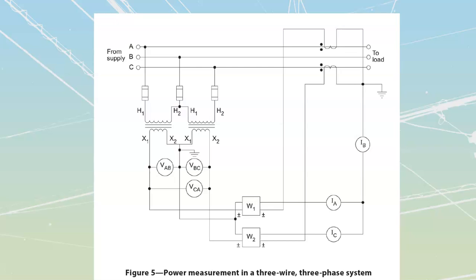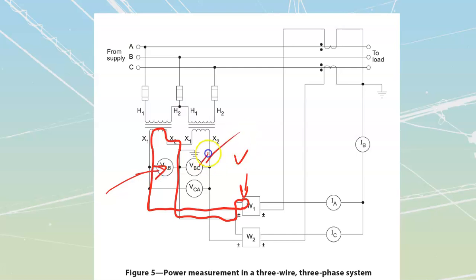Looking at my currents over here, we're just going to trace over top of stuff once again. Looking at this line over here coming from my watt meter, remember my watt meter is made up of a voltage element and a current element. Actually, that's not going to work. I'll trace it with a different color marker here. We'll just go with the red over here. If I take a look at my watt meter voltage element, which is what this thing is over here, I see that it is tracing this path over here, and then through the watt meter actual voltage element over there. So I see it's just measuring that loop over there. Yes, I do have this meter over here that's going to tell me voltage A to B, B to C, C to A, all those other voltages that we can get off the system. But we're not going to bother with those right now. We're just looking at this one over here for its voltage.